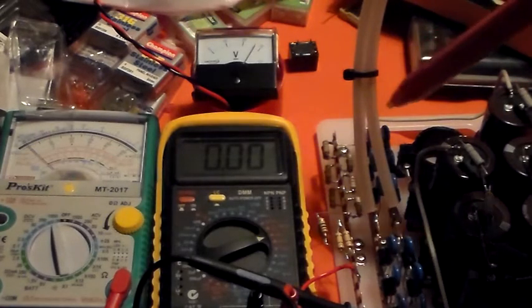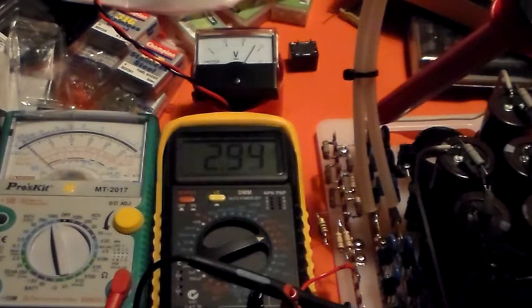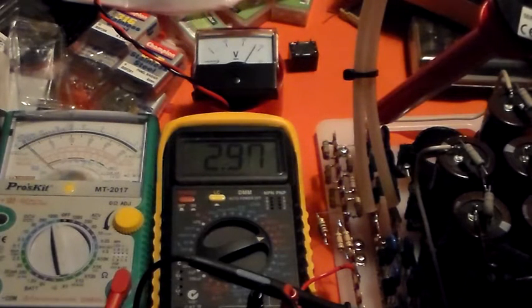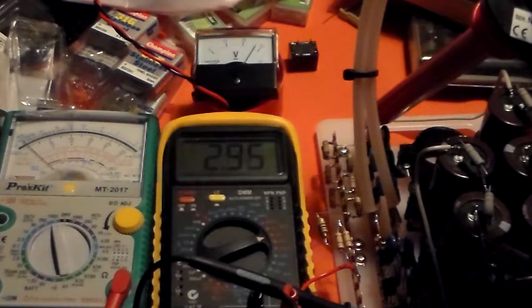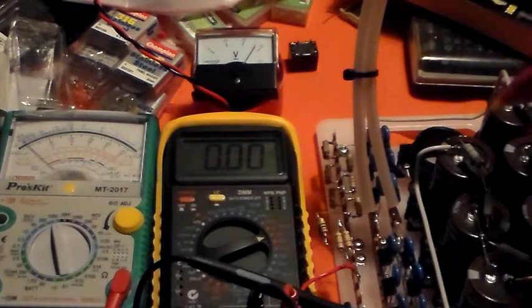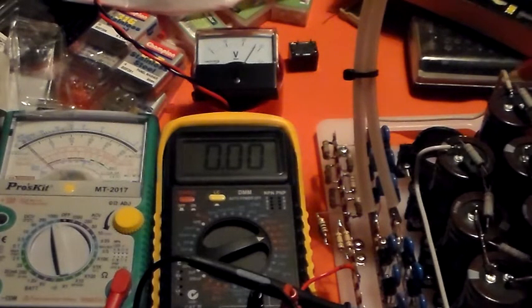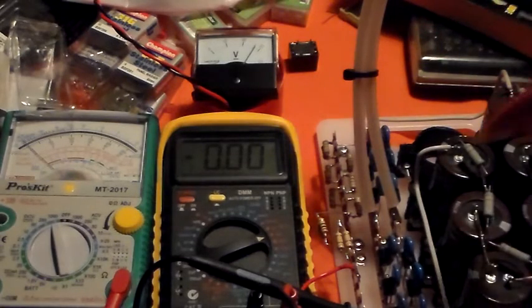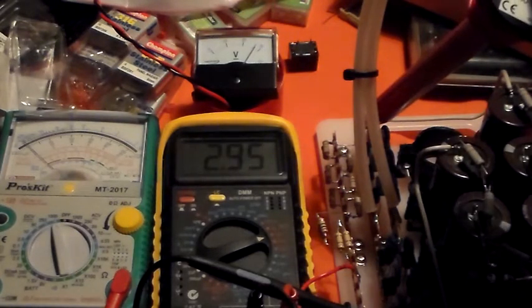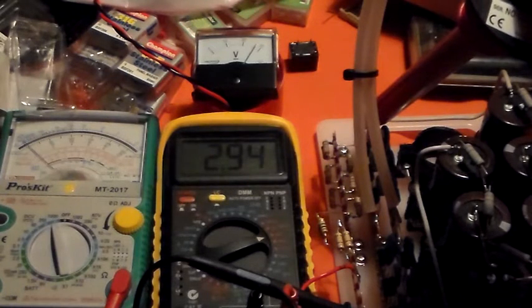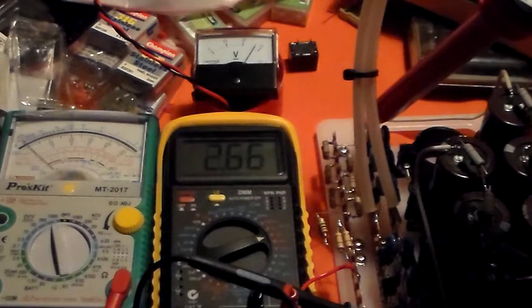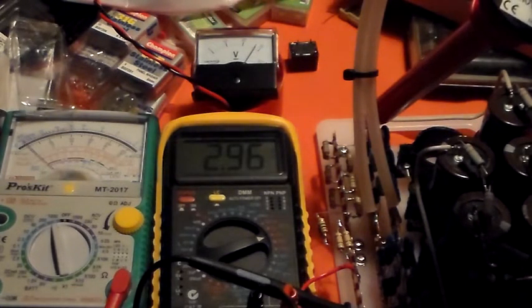Okay, so I'll put the high voltage probe on, and if you can see on that digital meter, it's showing 2.95. Okay, you're going to settle down. 2.96 - remember we've got very high balancing bleeder resistors here, very high resistance, so it's not providing much of a load to this power supply. When I put the 47Ks in, it'll stiffen it up a bit, be a bit better. So I thought this should be about 2800 volts, so that's saying 2.95, so that's 2950 volts. Yeah, there we go, get the probe on properly. 2950 volts.